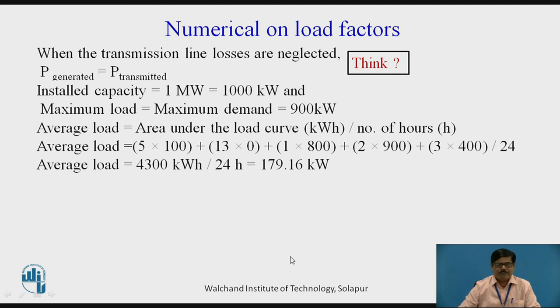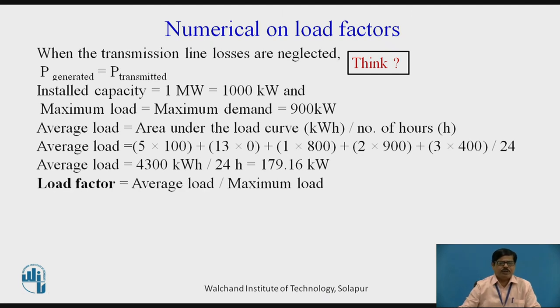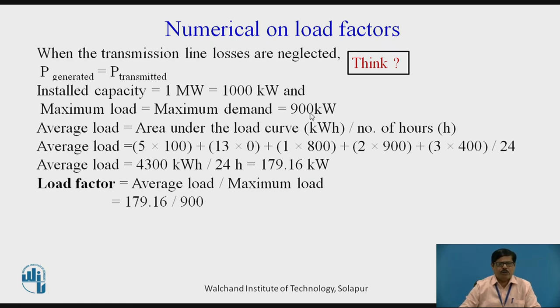Now we can find out the load factor, which is given by the formula: average load divided by maximum load. Average load is 179.16 KW, whereas the maximum load is 900 KW. When we calculate this, we get the load factor as 0.199, or 19.90%.